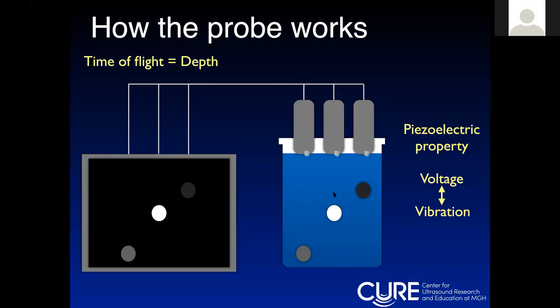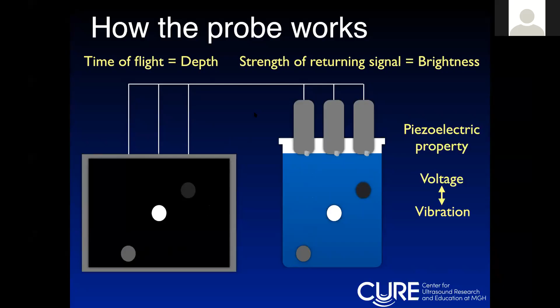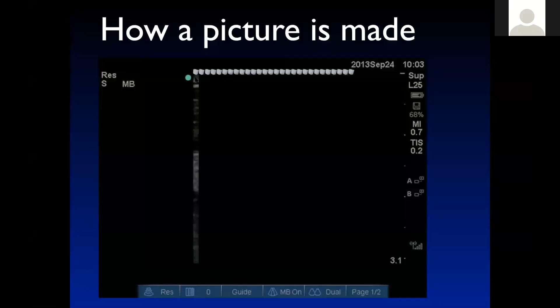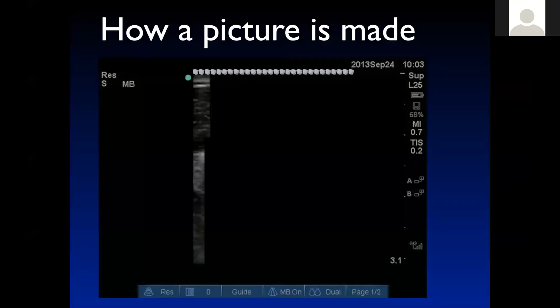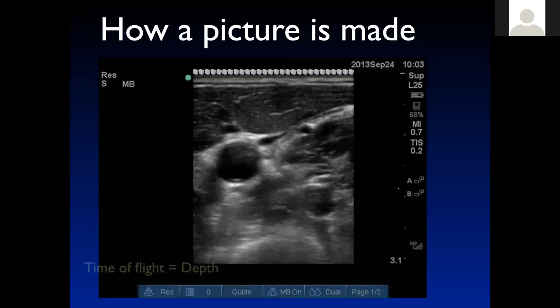And then the strength of the returning signal is also translated into brightness, right? And so what you're seeing here is that this one took longer to come back, so the probe knows it must be deeper. So time of flight, the duration of time that it took to hit this object, translates into the depth. The strength of the returning signal translates into brightness. And those are really the only two things you need to think about when you're talking about taking pretty pictures: depth and brightness. Now, every one of these crystals sends a quick blip of a signal. The stuff that comes back earlier, it puts up here. The stuff that took longer, it puts down here, right? And again, the strength of the returning signal translates into brightness. Its neighbor, this crystal here, does the same thing, and so on and so forth. And what you can see is that with time, an image of this carotid artery and compressed IJ is generated. That's how pictures are made.